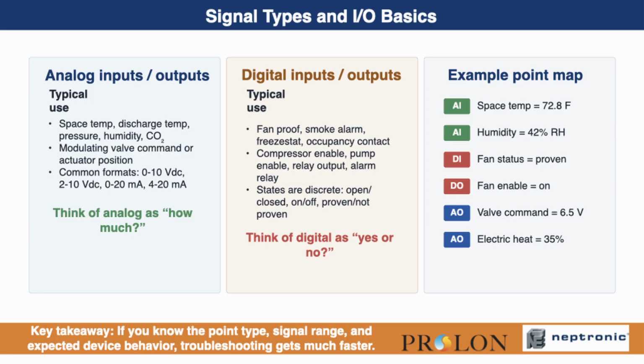At this point, we connect field devices to controller language. Inputs and outputs are usually classified as analog or digital. Analog means the value varies across a range, such as temperature, humidity, pressure, or a modulating command like 0 to 10 volts to a valve actuator. Digital means the signal has two states, such as on or off, open or closed, normal or alarm. This gives us AI, AO, DI, and DO, analog input, analog output, digital input, and digital output.